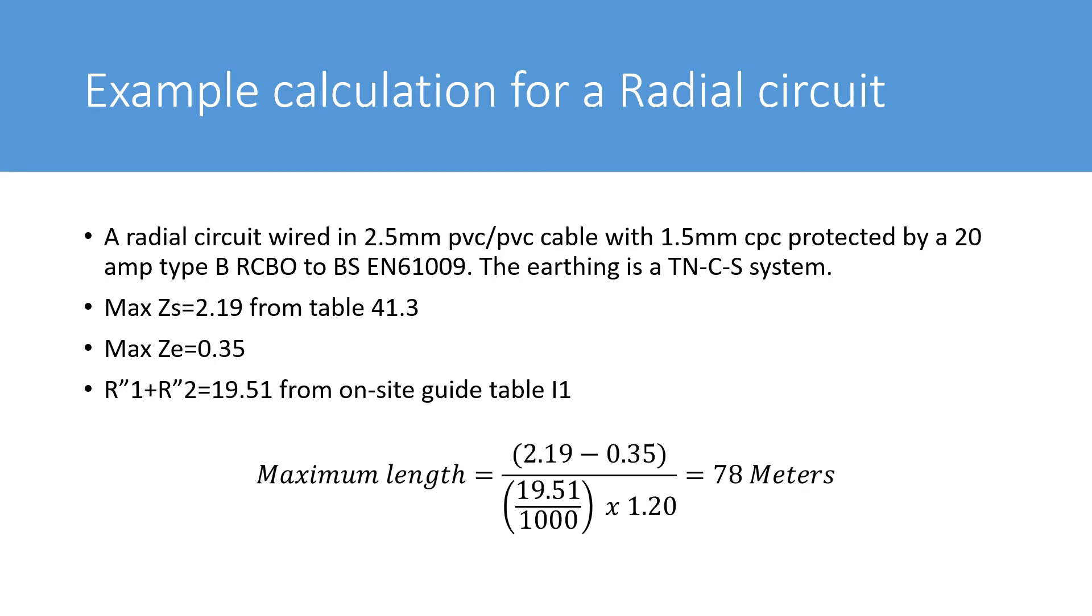So if you look at the table, you'll see a list of different sizes of cable, combinations of different line conductors and CPCs. And if you look for the 2.5 mm line conductor with a 1.5 mm CPC, you'll get the value of 19.51.